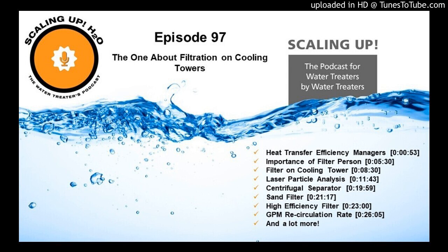I think the most popular filtrations that I've seen on cooling towers are either a sand filter or a centrifugal separator. Do you mind talking about what the differences are between those two? Sure. A centrifugal separator is a mechanical unit that depends on spinning the water and causing a centrifugal force to push the particulate outside, where it agglomerates together, drops down to the bottom and comes out. Generally, a centrifugal separator is going to take out 70 micron particles, and those are fairly large particles. You're not removing any of the pollen, for example, or any of the fine particulate with a cyclone separator, a centrifugal separator. So water treaters generally don't recommend them.